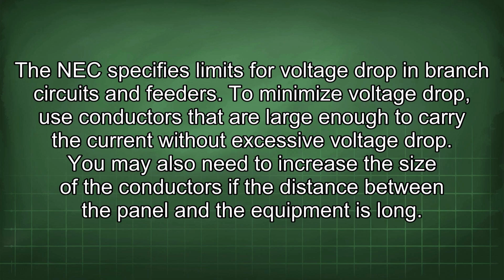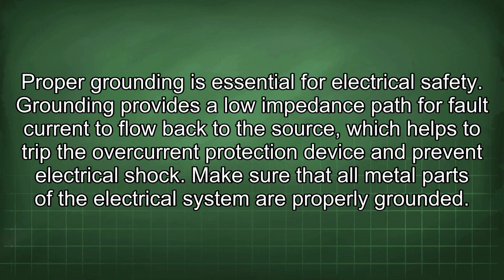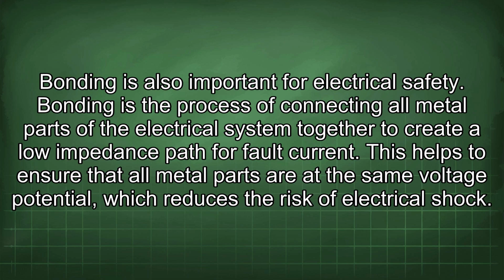Proper grounding is essential for electrical safety. Grounding provides a low impedance path for fault current to flow back to the source, which helps to trip the overcurrent protection device and prevent electrical shock. Make sure that all metal parts of the electrical system are properly grounded. Bonding is also important for electrical safety.